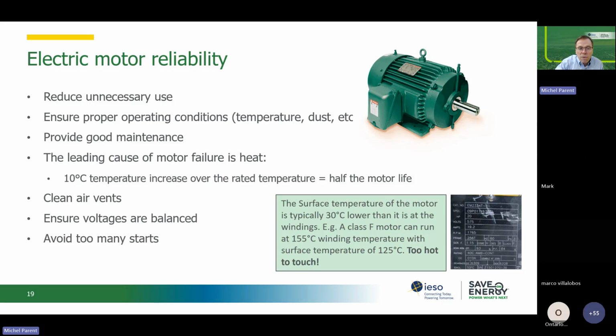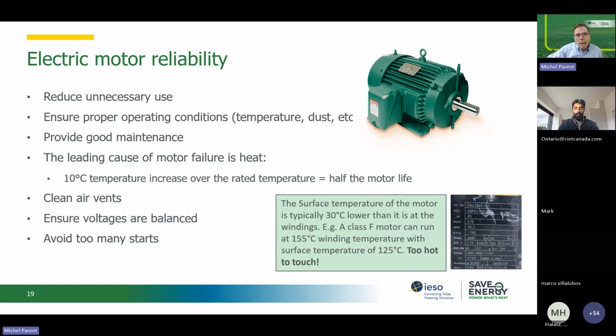And by the way, that 155, it's rated for 40 degrees indoor temperature. So if your indoor temperature is 20 degrees, then your winding temperature should be 20 degrees less. So it should be at 135. And your surface temperature should be 30 degrees less than that, so it should be 105.